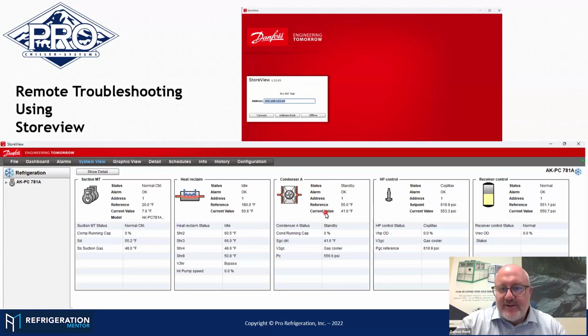We jump over to the condenser side of things. Everything's happy. What's my reference, my current value? Same thing. I can see if I've got a bypass valve, am I in gas cooler mode? Am I in bypass mode? What's my pressure? Right now I'm sitting idle, and I don't mind seeing 560 PSI there. Jump over to my high pressure control. This is where I'm controlling the high pressure control valve. I've got a current value of 550 and a set point of 619. Well, that valve shouldn't be open at all right now. And it's not, it's off.